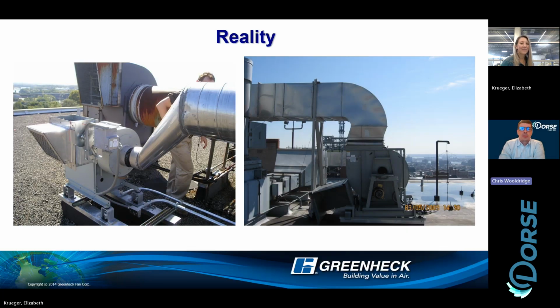We are running the fan at a constant RPM, and we take live pressure and volume readings. So we're not adjusting anything on the fan. We're just making adjustments to the ductwork, and it is crazy how impactful the duct is on the fan performance. And I think it's something that everyone takes home. Sam clearly remembered it. It's impactful, and if that's what you learned from the trip, then we're doing our job, right? Because that's something Sam's going to take forward on every job he works on. So Elizabeth saw me pop on the screen. This is a big focus of mine in helping engineers design. All right, I'll be quiet now. I'll let you take back over.